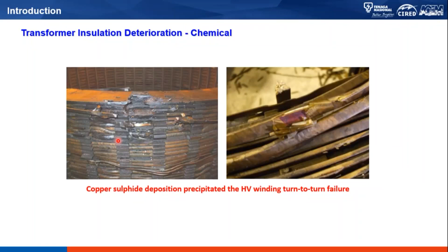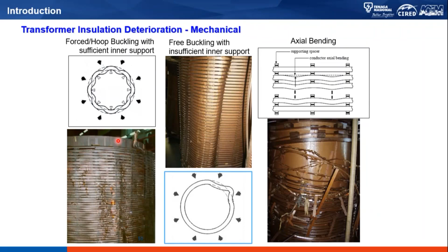Okay, next is the mechanical stress. You can clearly see that these windings are deformed way beyond words. Of course there are terminologies given to this kind of deformation. The one on the left is what we call the forced hoop buckling, then the free buckling, the one in the middle, and then we have the axial bending. It's actually the winding collapse that you can see in the photo on the right. Okay, so these are what we call the mechanical stresses. These are no longer stresses, these are actually signs of failure on the transformer itself.